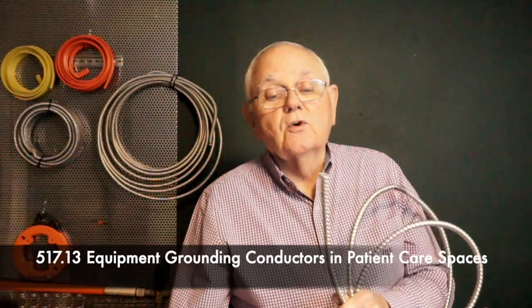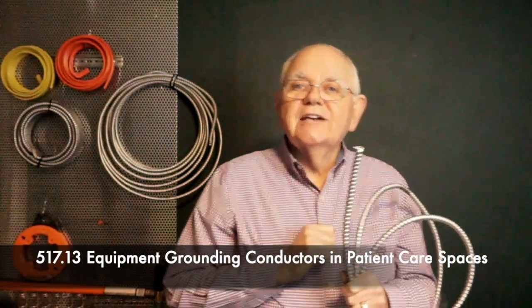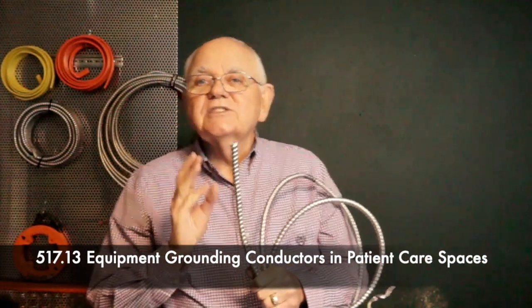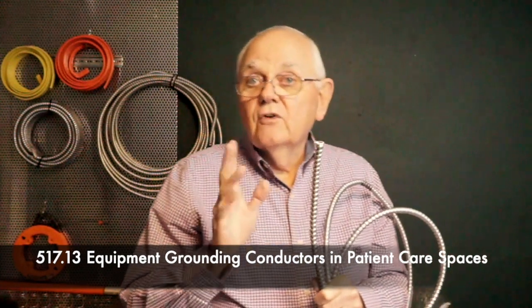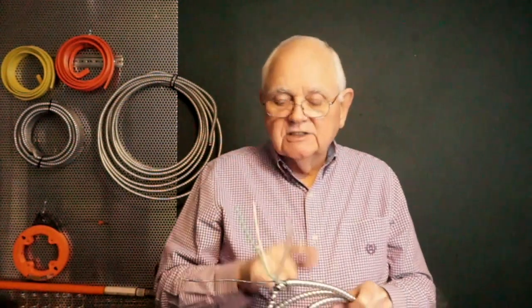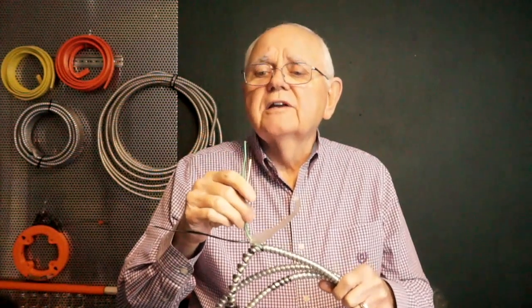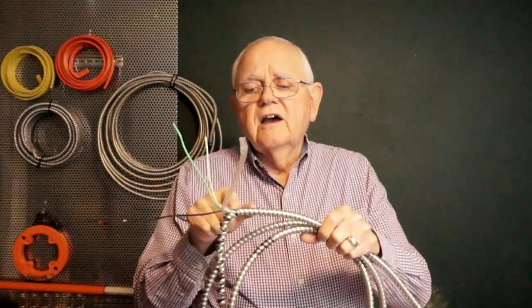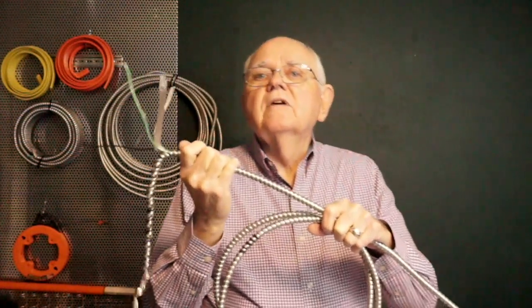517.13 talks about this equipment grounding conductor in patient care spaces. So in patient care spaces in hospitals, I have to have two equipment grounding conductors. I have to have a redundant equipment grounding conductor. So what I can do is, in a healthcare facility, if I'm going to use some in patient care spaces, I'll use the green insulation. That will be one equipment grounding conductor then. And then if I have that bare conductor that runs the entire length, that makes my sheath the equipment grounding conductor as well, then I can certainly use that.